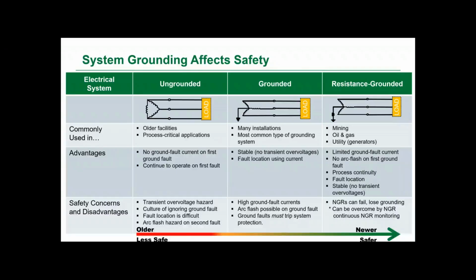Now, as you move to the right with resistance grounded systems, it blends the advantages of both those ungrounded and solidly grounded systems. So a high resistance grounded, or you might hear it called a high impedance grounded, or a system with an NGR, which is a neutral grounding resistor. Those systems can still provide continuous operation on a ground fault, and still allow a safe amount of current to flow and for the fault to be quickly located.